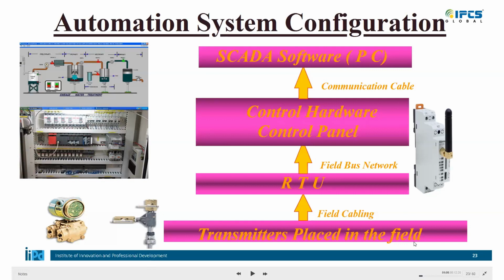If it's just a few meters, a few hundred meters long, we can go for remote IOs. But if you're talking about very long distance communication, maybe a pumping station 50 km away from my plant, and I want to get the data from that pumping station to my plant, then we go for RTU systems. Then we have the control hardware.